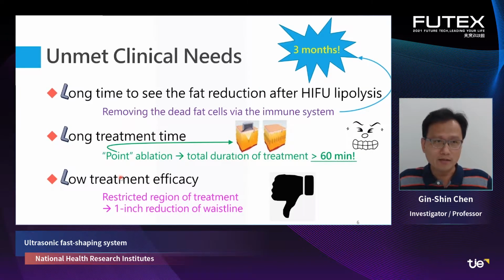The current HIFU lipolysis technology has some drawbacks. The first is people wait for a long time to see the outcome after treatment. It's usually 3 months because removing the broken fat cells is via the immune system. The second is people lie on the bed for more than 1 hour for treatment because the current technology hits the fat point by point. We call it point ablation. The last is people feel the treatment efficacy is low. The point ablation limits the region of treatment and only achieves 1 inch reduction of waistline.